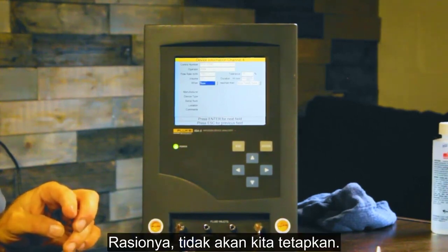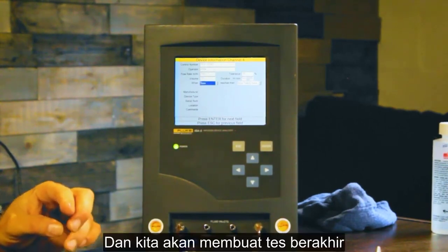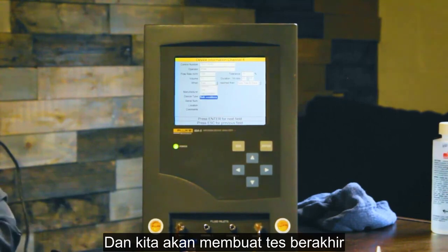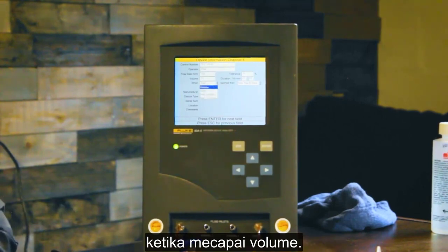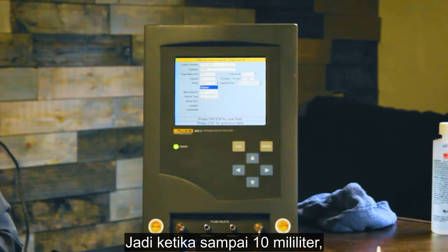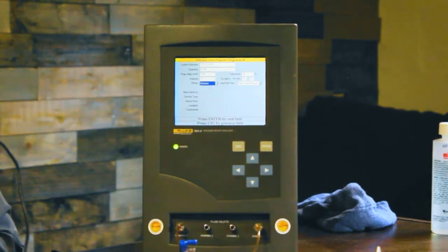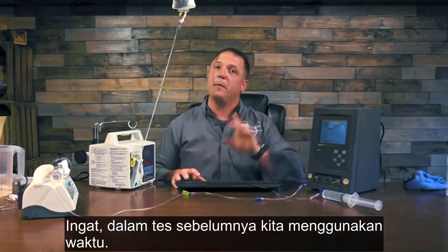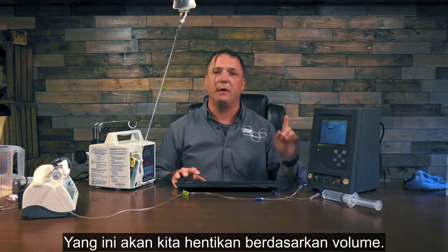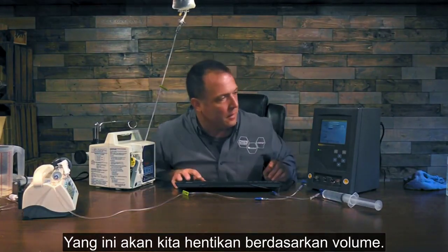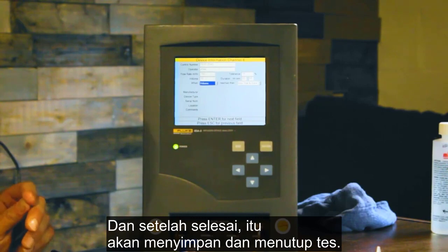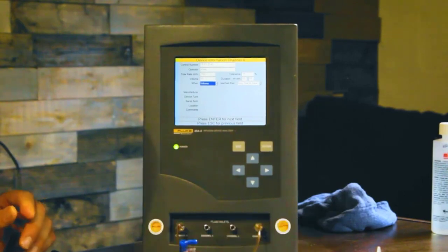Duration, we're not going to set. And we're going to have the test end when it hits the volume. So when it gets to 10 milliliters, this test is going to stop. Remember in the prior test we used time. This one we're going to stop it by volume. Alright, and when it's done it's going to save and close the test. Alright, hit enter.